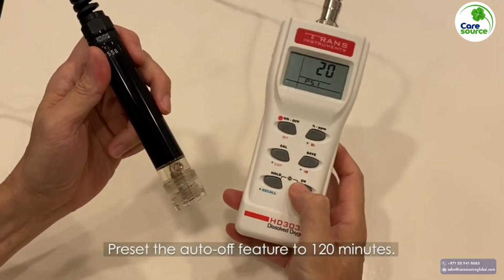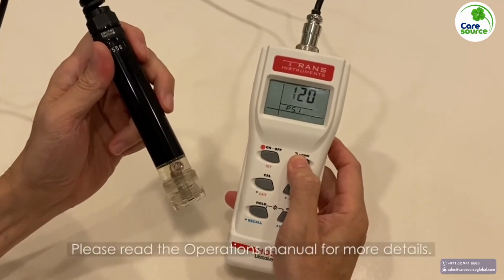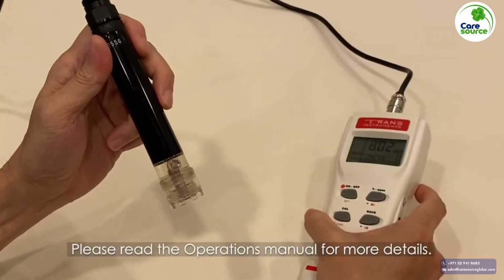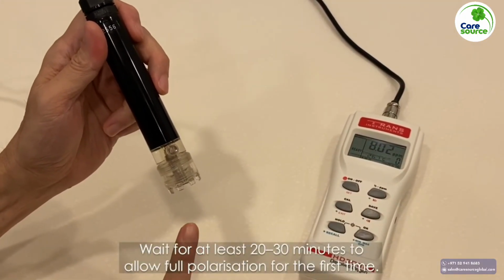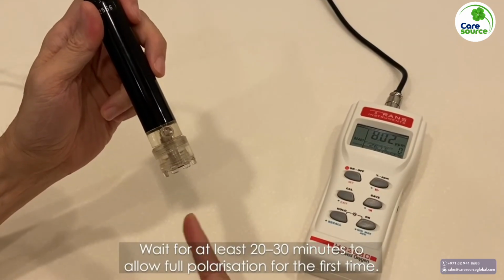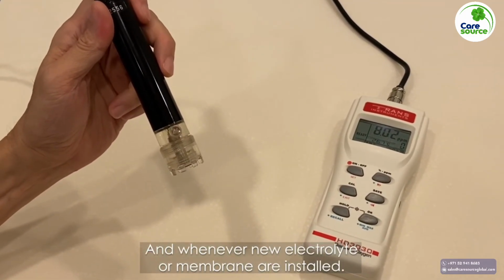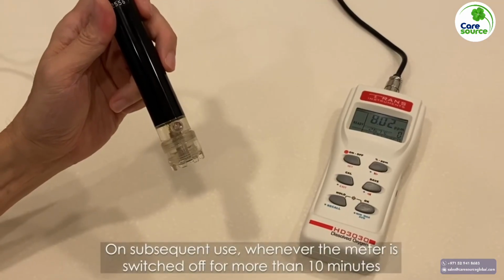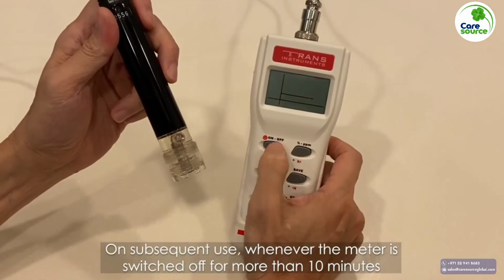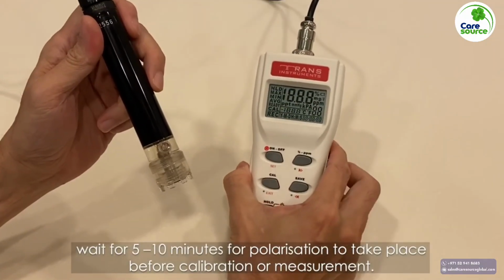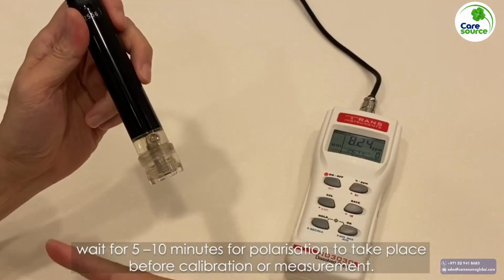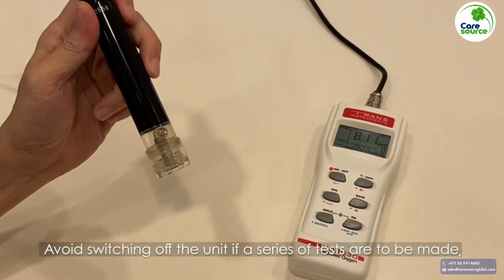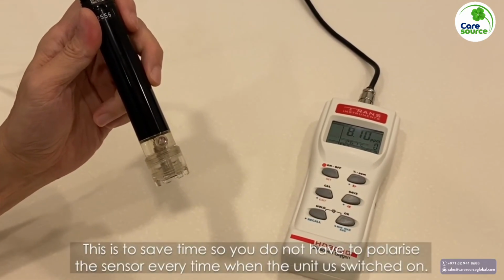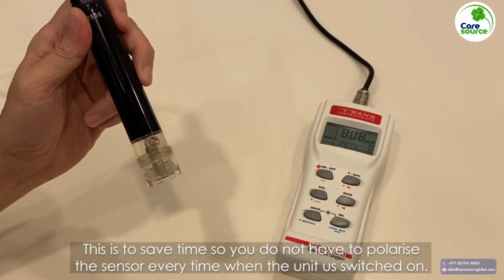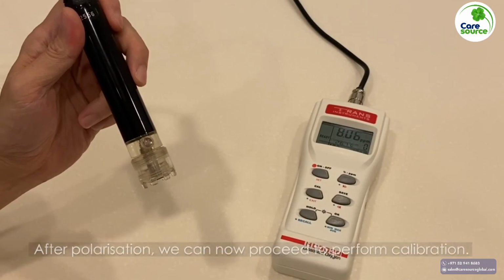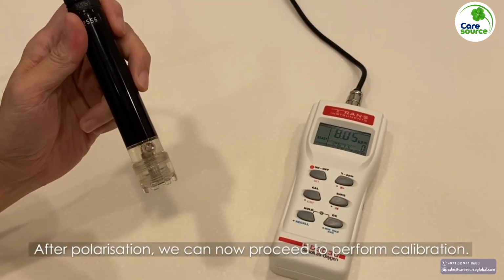Preset the auto-off feature to 120 minutes. Please read the operation manual for more details. Wait for at least 20 to 30 minutes to allow full polarization for the first time and whenever new electrolyte or membrane are installed. On subsequent use, whenever the meter is switched off for more than 10 minutes, wait for 5 to 10 minutes for polarization to take place before calibration or measurement. Avoid switching off the unit if a series of tests are to be made. This is to save time so you do not have to polarize the sensor every time the unit is switched on. After polarization, we can now proceed to perform a calibration.